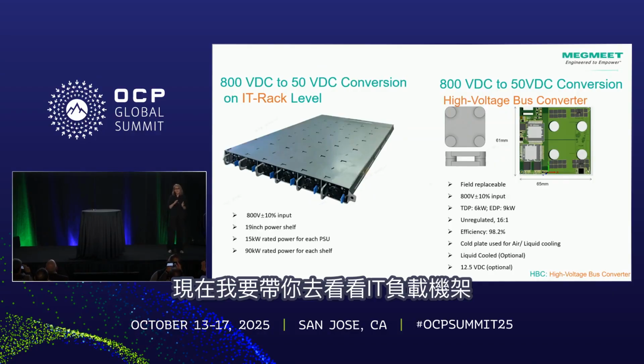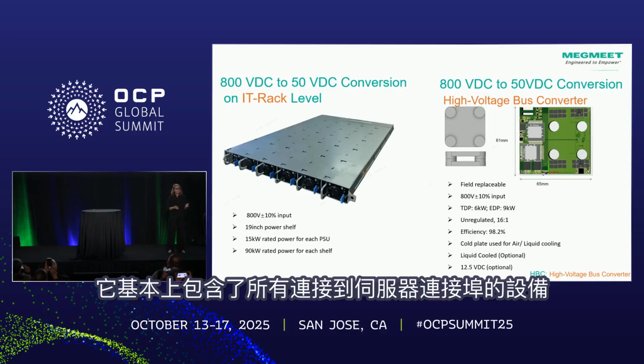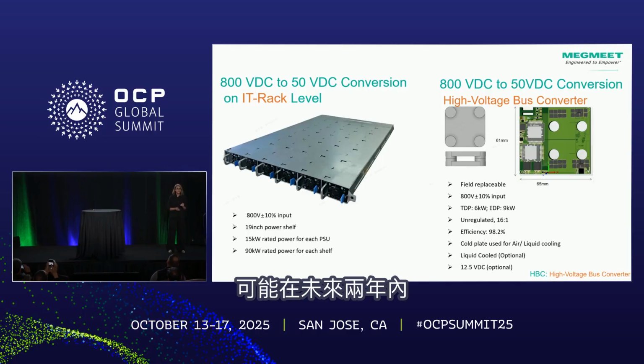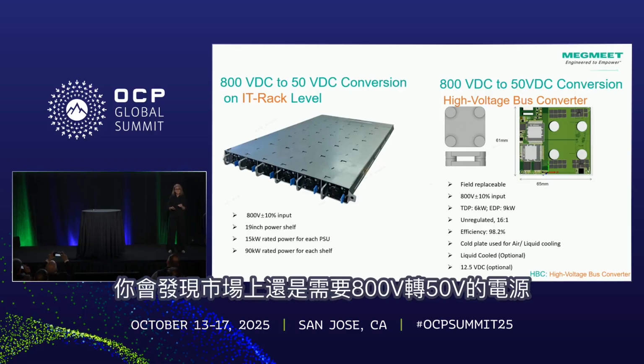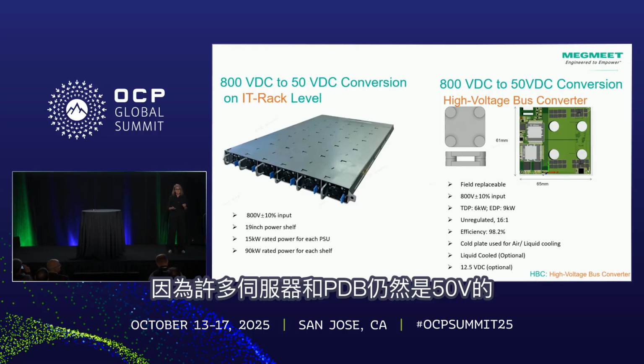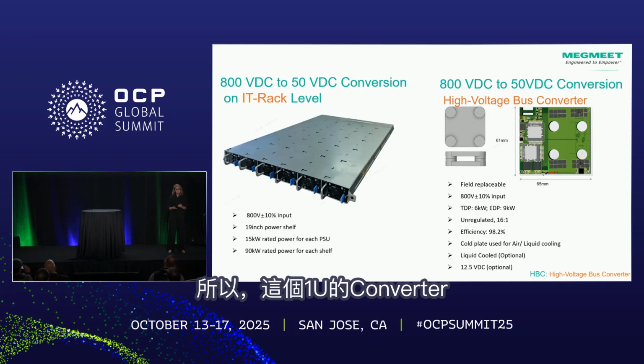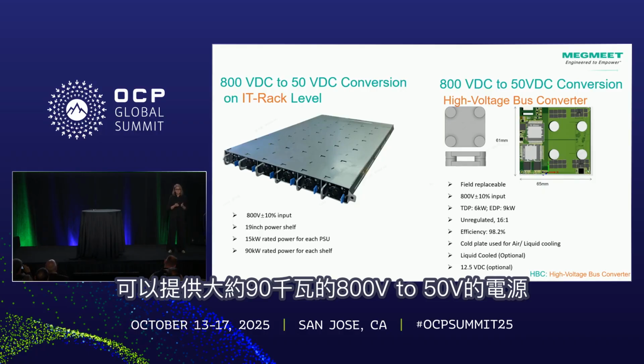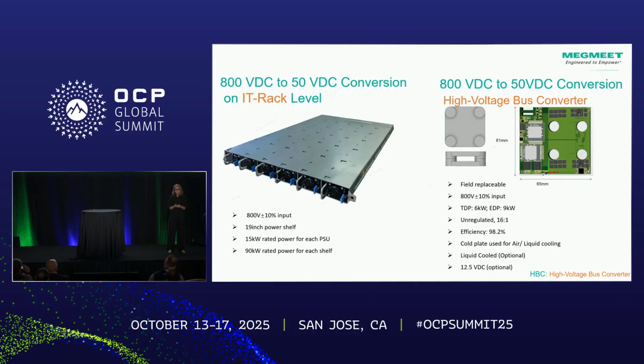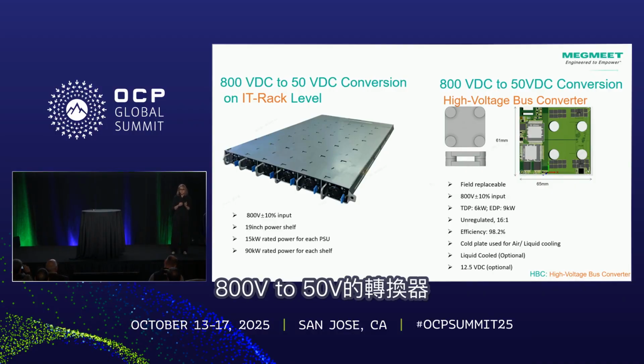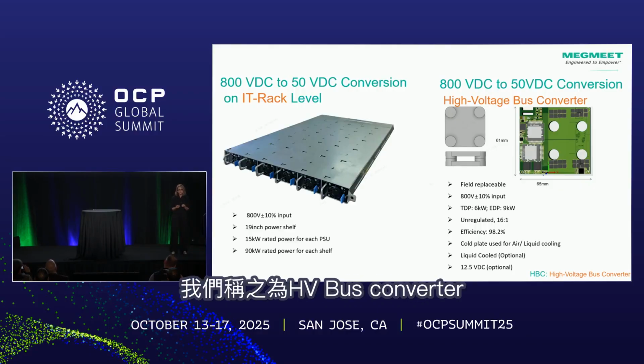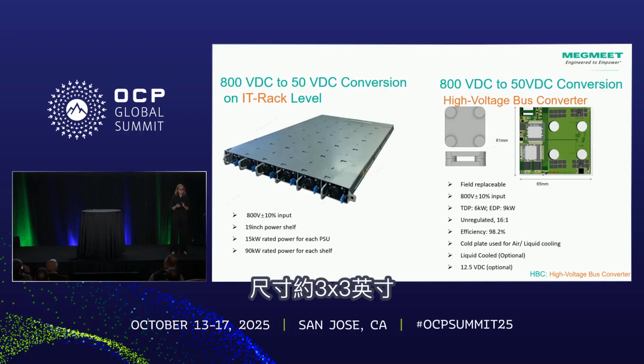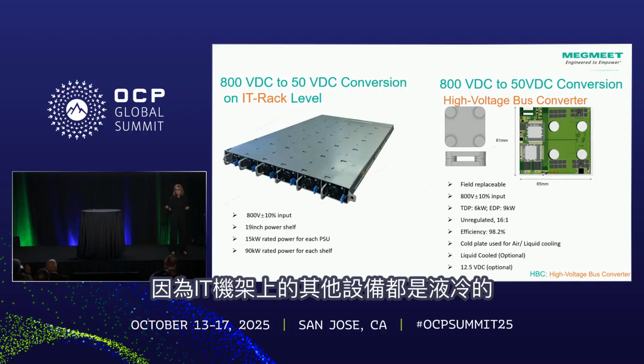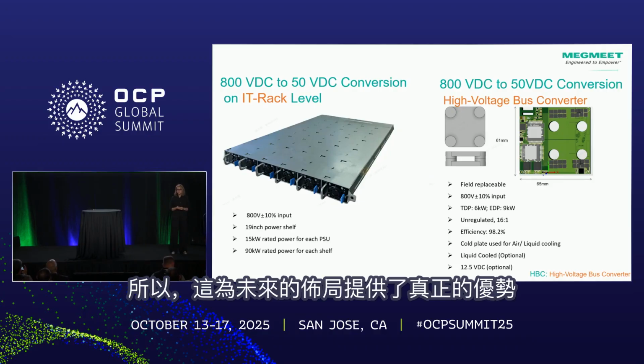Now I'm going to take you to the IT load rack. This is basically everything that is going into the server board. Probably for the next 2 years, you will see that 800 to 50 is needed because the server and PDB is still at 50 volts. So that conversion at about 90 kilowatt in 1U is giving you the DC to DC ready for distribution on the IT load. On the right side, you can see that the 800 to 50 volt intermediate, we call it high voltage bus converter. That is 3 by 3 inch approximately, and definitely has to be liquid cooled because everything else on that IT shelf is liquid cooled. So this is giving a real advantage in moving forward for any future distribution.